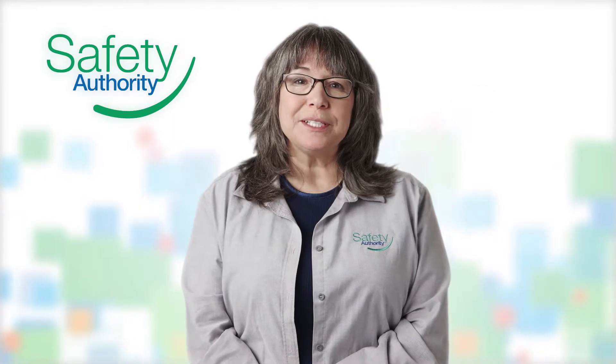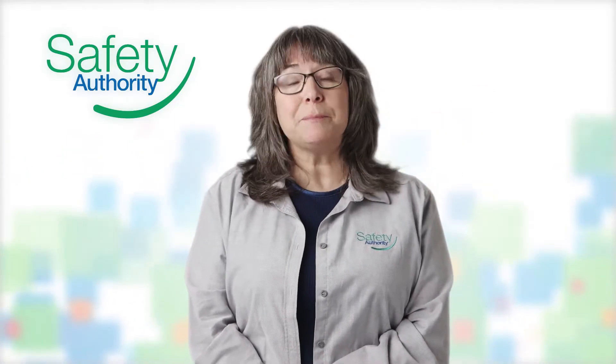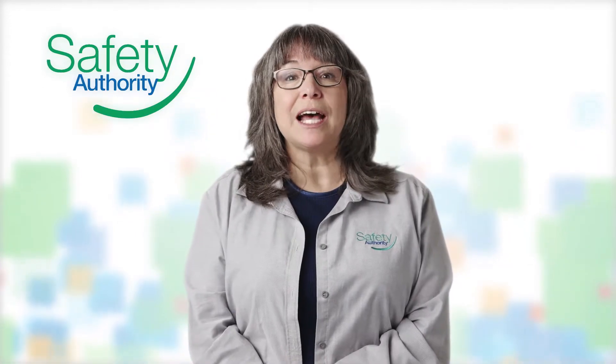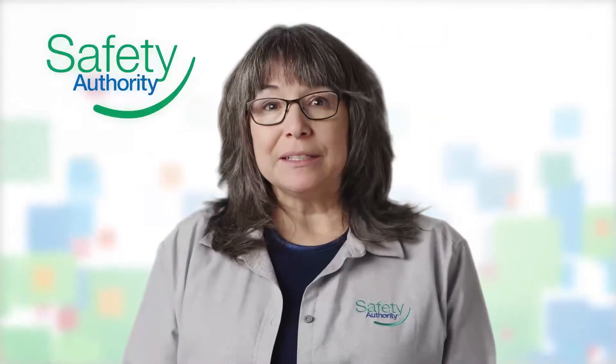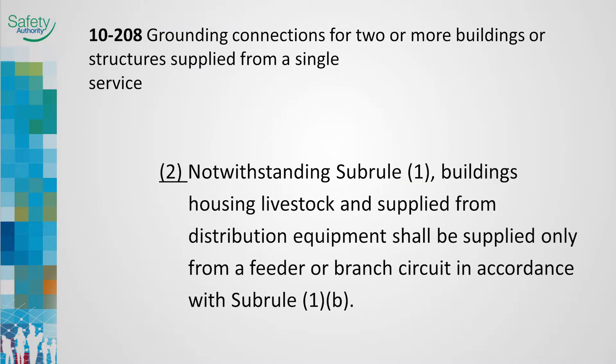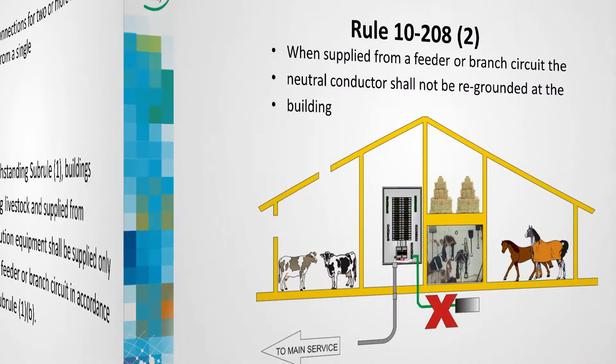Rule 10-208, sub-rule 2 is new and requires that buildings housing livestock have their neutral and bonding circuits isolated from each other. Grounding the neutral at a building is no longer permitted. This means barns and similar structures supplied from a distribution system located elsewhere on the property shall be supplied with a feeder incorporating a bonding conductor, and the neutral bonding screw shall be removed.